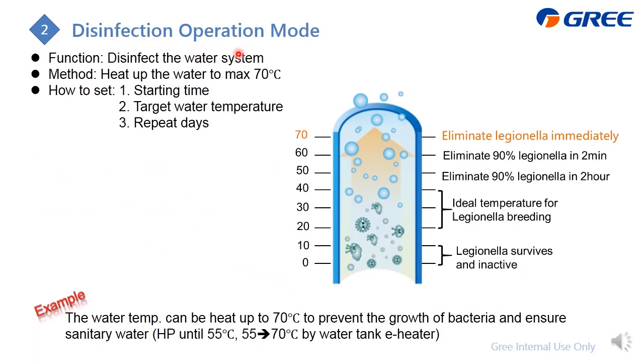Disinfection operation mode. The purpose of it is just to disinfect the water system, and the method is just heating up the water temperature. What you can set is when to do it, the target water temperature, whether you need to reach the max 70 degrees, and the last is how often to do it again. For example, if we need to heat up to the maximum 70 degrees to clean the water, the heat pump, which is the compressor, is only heating up to 55, and from 55 to 70 degrees is heated only by the water tank e-heater.